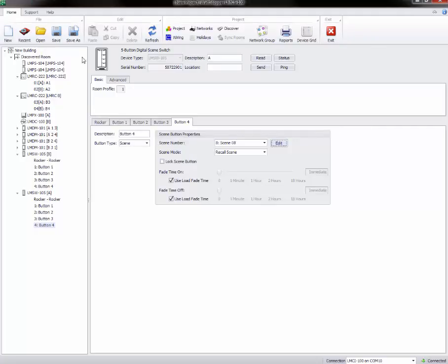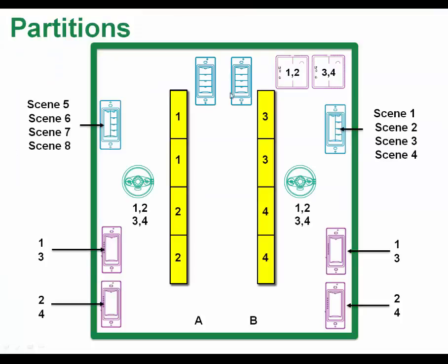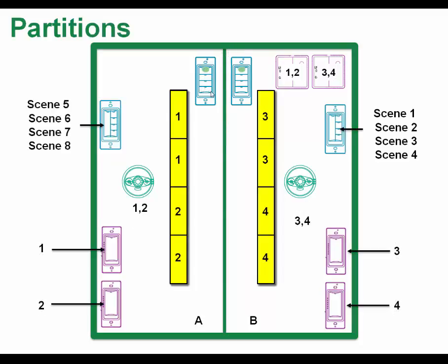So I've got this room set up just like this. Okay, so now I'm going to close the partition. Usually it takes between 4 and 5 seconds for the profile to actually activate in the room. I want these bindings to happen. And when I talk about scene 5 now, it's going to be all loads 100, 75, 50, 25, but I only want to control loads 1 and 2. So we're going to have to change those bindings.